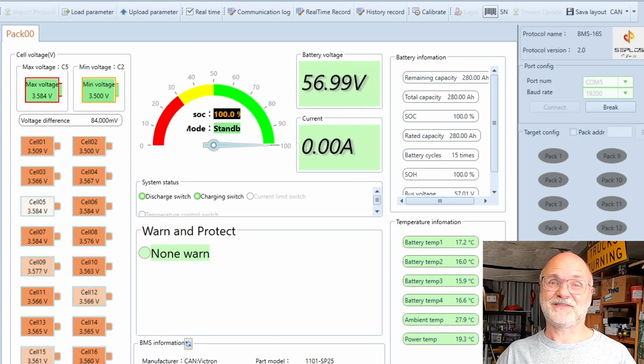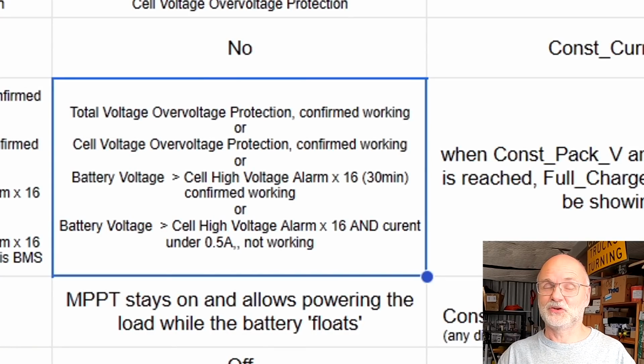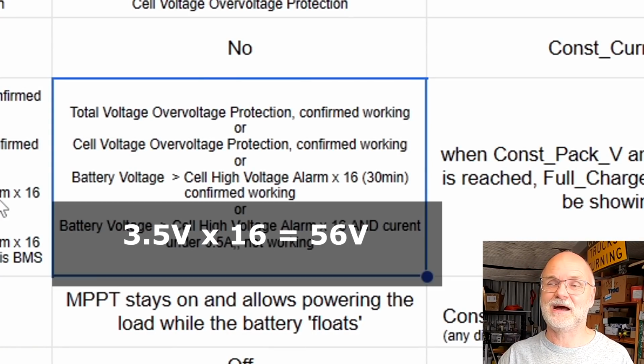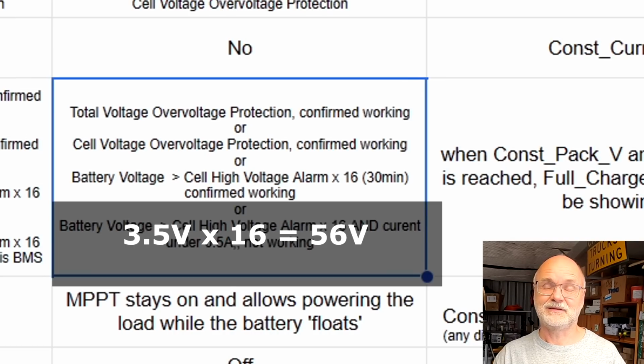So the only thing we need to test now is whether the BMS actually resets to 100% after half an hour. Our battery voltage needs to be higher than our cell high voltage alarm, which is 3.5 volts in our setting, times 16. So the battery voltage needs to be higher than 56 volts for half an hour. Let's see if the BMS resets to 100%.